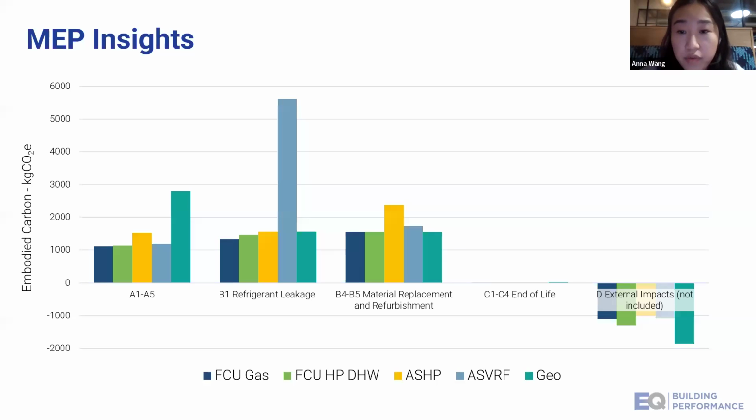Another consideration for refrigerant leakage is that there is no drop-in replacement for your equipment. And then at the end of the life, you may want to abandon that system due to phasing out of current high GWP refrigerants. Therefore, it's important to consider, and we review, refrigerant type and replacement opportunity, and adjust for refrigerant leakage and volume within your mechanical architecture.